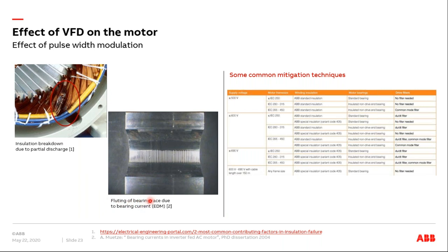The second picture is how the bearing is damaged. Because of this current flow from the stator to the rotor, you would have a differential voltage on the bearing, because a bearing has two sides, with the bearing balls and also an insulation layer. Because there's a potential difference between the two sides, you have this EDM, or electrical discharge machining effect going on. It's basically like welding.